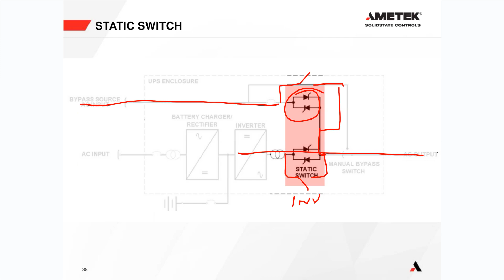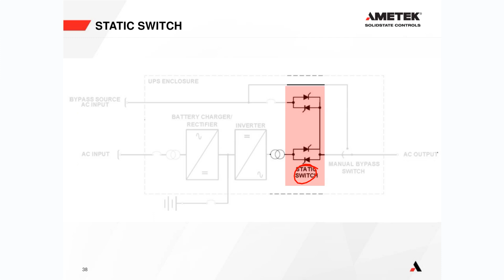Basically, what we can do is switch the inverter switch on, and that allows power to flow from the inverter to the output. Or we can turn the bypass switch on, allowing bypass to go to the output. Now, the reason it's called a static switch is there are no moving parts. There is no mechanical switching, and I'll explain in a moment how we do that.